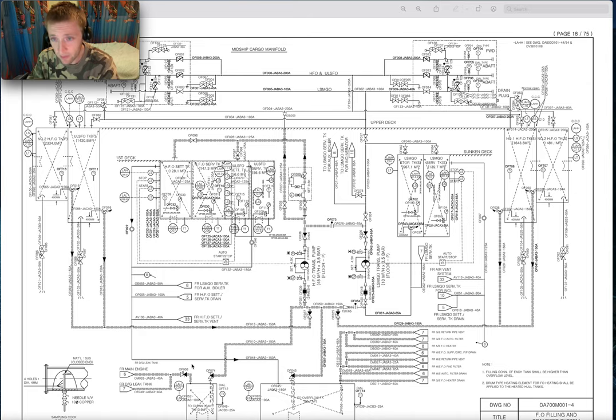Down below in that piping, let's say these are the two filters, the fine filters, the last filters, which are attached locally to the diesel generator, and there are buttons down on these filters and two pipes going here, and after that they connect to one common pipe, and about 30 or 40 centimeters along, this pipe must be about engine room temperature. So if I observed that there is an increase of temperature, that means it has leakage, and it was more difficult to detect when you have diesel running to your diesel generator, because diesel has about the same temperature as the surrounding area of the engine room.